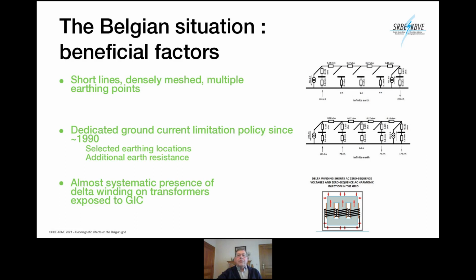put to the earth at both ends, and the second one the same line, but with three intermediate transformers and connection to Earth. And what you see is that the currents, which are 250 amps in the first example, drop to 150 and 100 or something like that in the second case, which means the total current of the first case is subdivided in minor currents in the intermediate points. This is beneficial for each individual transformer, of course, because it has less burden from the DC current.